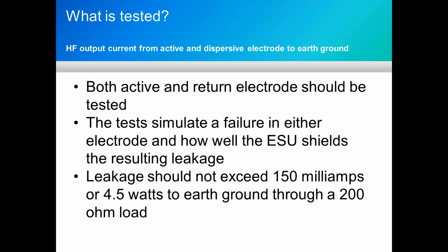High frequency leakage testing is always done in single fault conditions, just like when we do our electrical safety testing. But here we're going to do single fault conditions where either the active or the dispersive patient return or dispersive bipolar leads are open. They simulate a failure in a connection somewhere in the circuit itself. And there is a limitation set by the standard as to how much leakage current can be allowed. And that standard says 150 milliamps through a 200 ohm load.